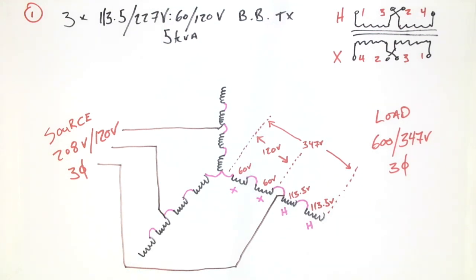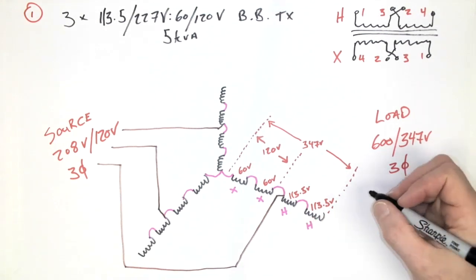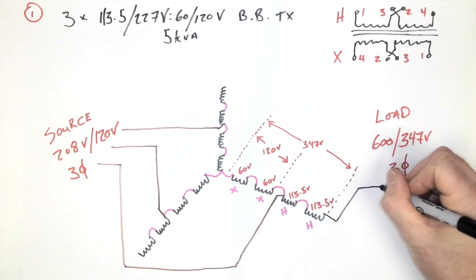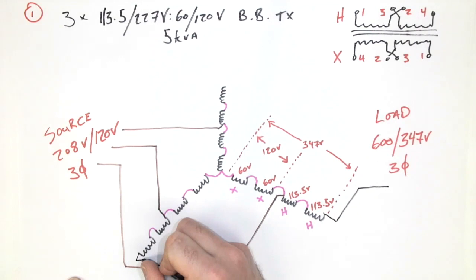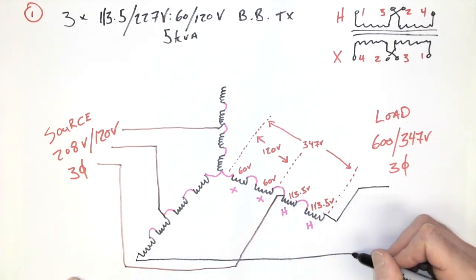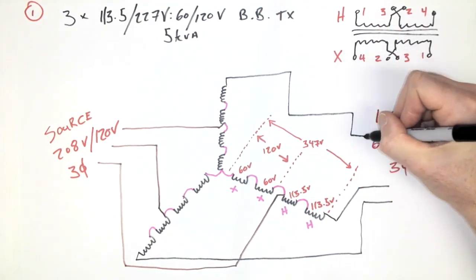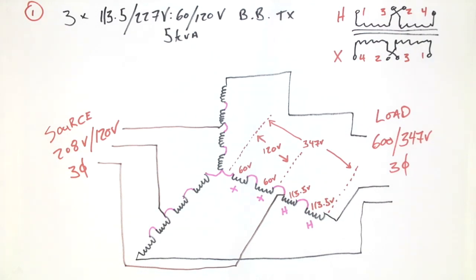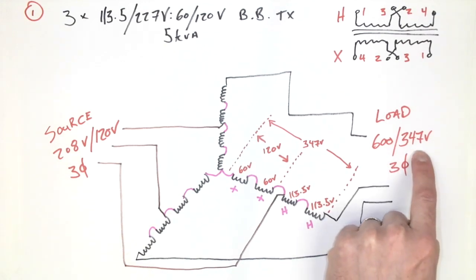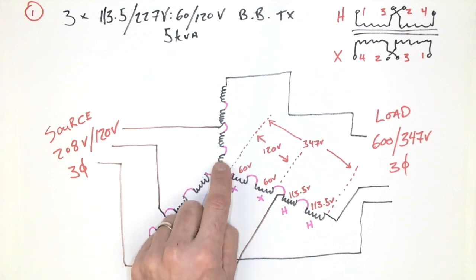The next one we're going to do is the load connection, and the load connection needs to have a 347 volt value for the phase, which means we are connecting to the outer reach of each one of the star arms. So I'm going to head over to that one. This one goes all the way across and up, and this one like that. All right, so we've got 3 connections for the load, 3 connections for the source. If the load required a neutral connection, we could take a 4th conductor right out of the center, and that would then be our neutral.